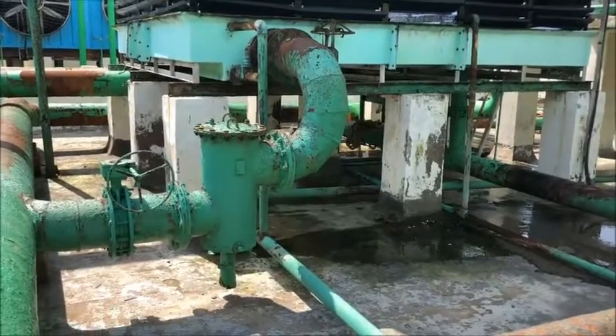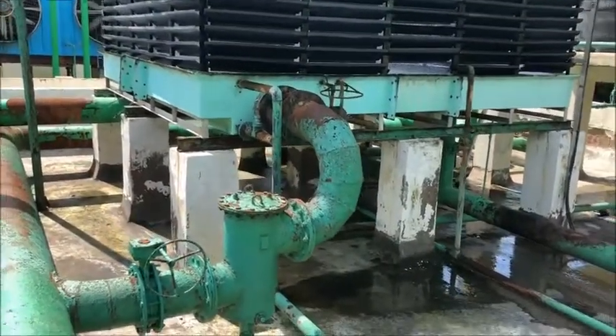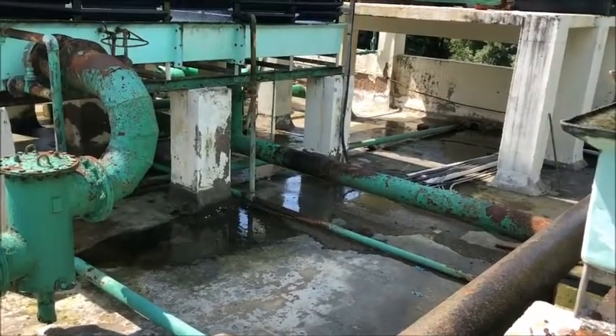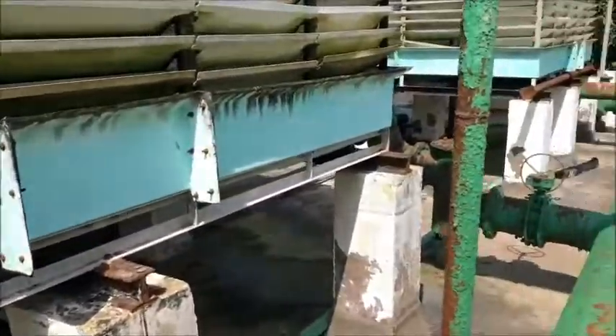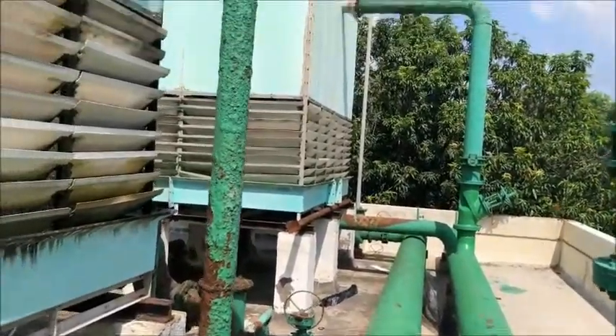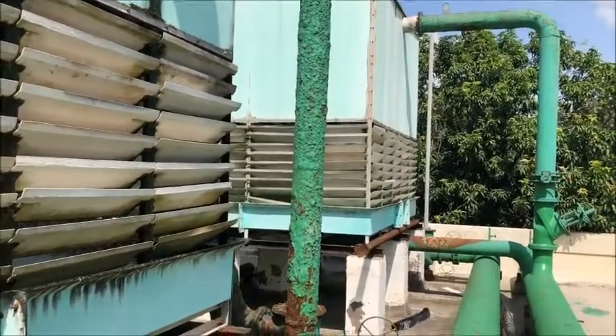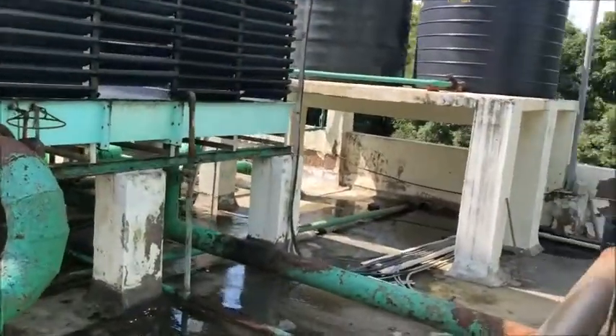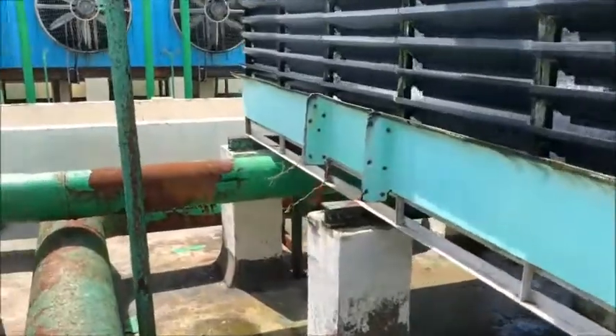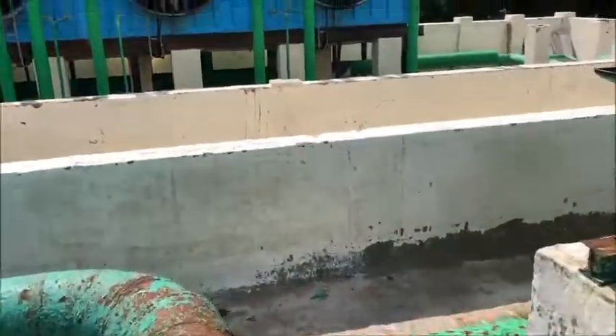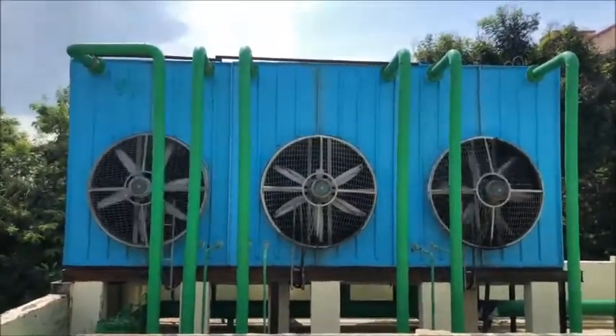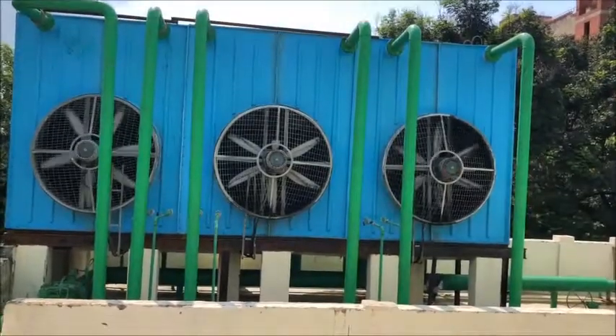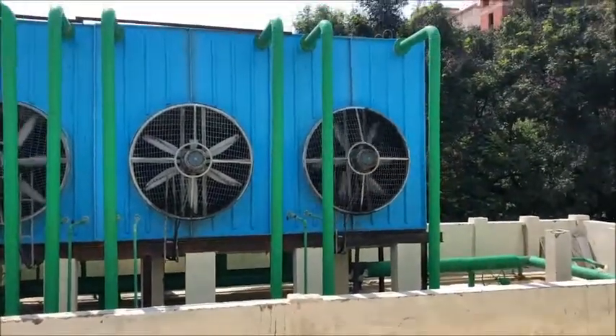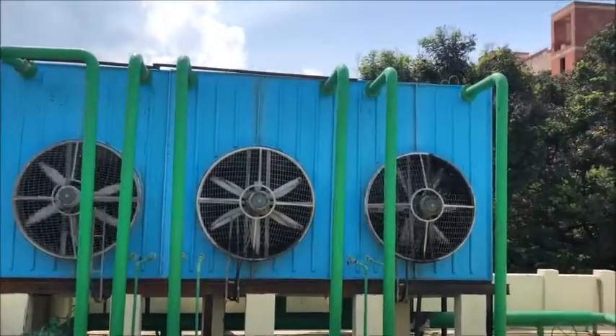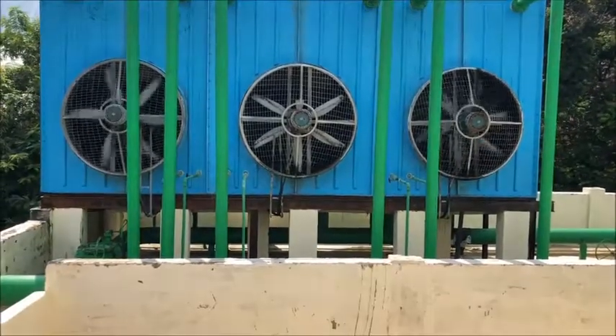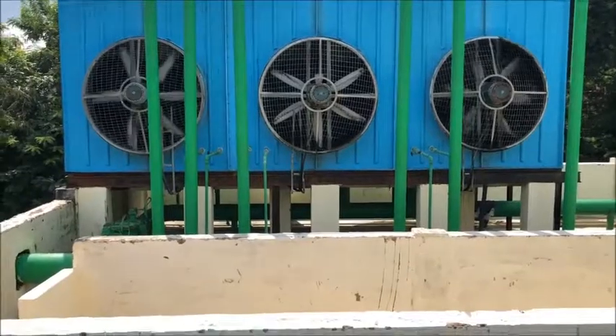And at the base of the cooling tower, this is a base sump. So basically these cooling towers have been designed on an approach of 5 degrees Celsius. So 35 degree water coming from the condenser gets cooled to 30 degrees Celsius under normal ambient conditions. But during peak monsoon season, the rate of evaporation reduces because of the increased humidity in the environment. Now we have another set of cooling towers which have been installed in the last 1.5 years, and we have gone for the forced draft cooling tower. As you're seeing, this cooling tower is of capacity 450 TR, with 3 cells, 3 pass, each of 150 TR capacity.